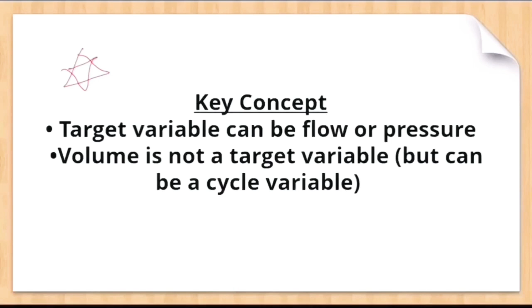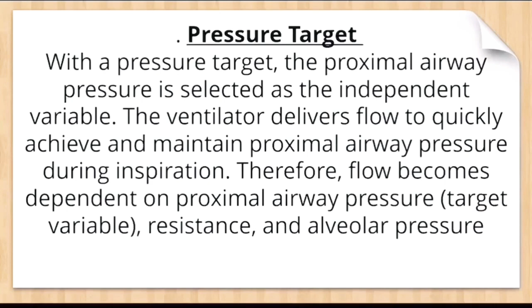Now pressure target. With a pressure target, the proximal airway pressure is selected as the independent variable. The ventilator delivers flow to quickly achieve and maintain proximal airway pressure during inspiration. Therefore, flow becomes dependent on proximal airway pressure, that is the target variable, resistance and alveolar pressure. So the ventilator will deliver the flow quickly to achieve that proximal airway pressure that we have selected as the target.